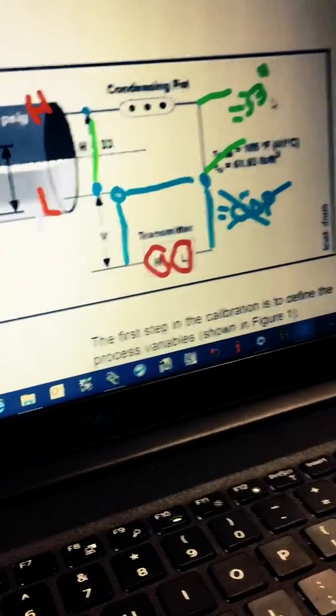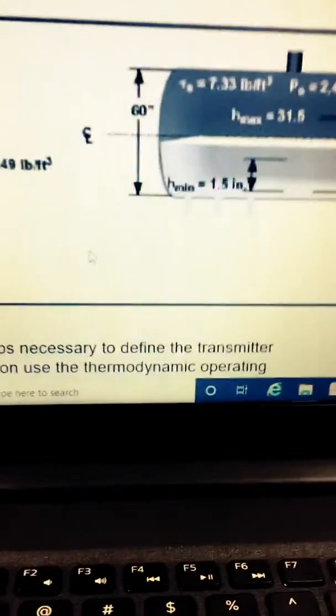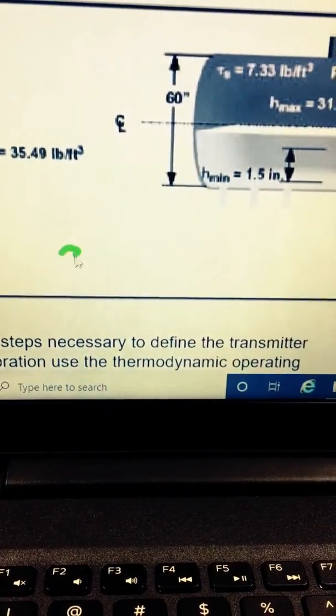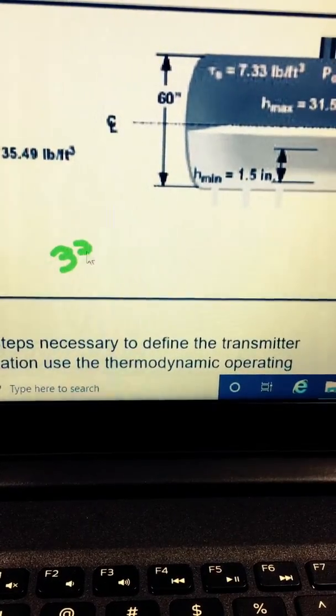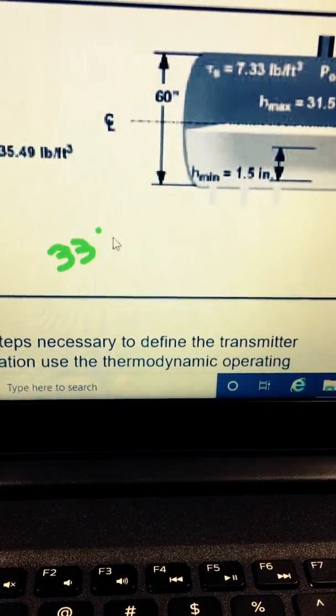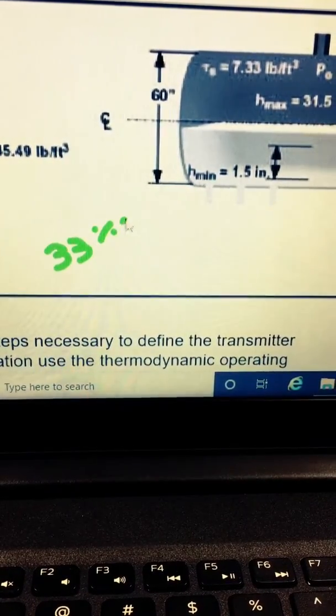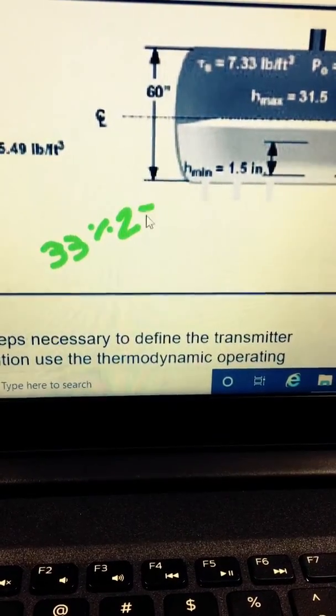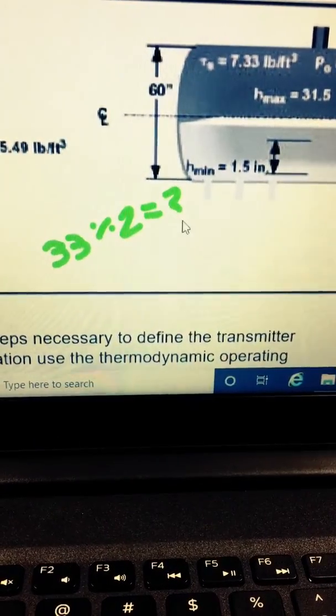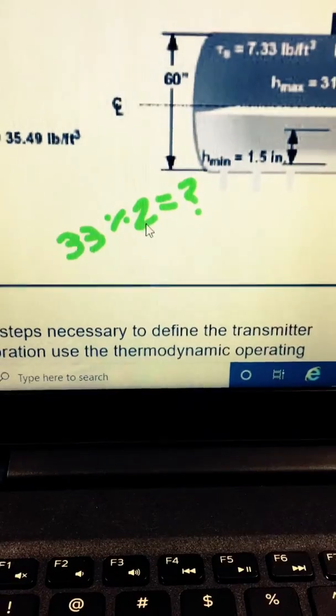So, 33 inches. Alright, so from the low of the drum to the high of the drum tap, we have 33 inches. And we're going to divide that by 2. And that's going to give us our values for upper range and lower range.